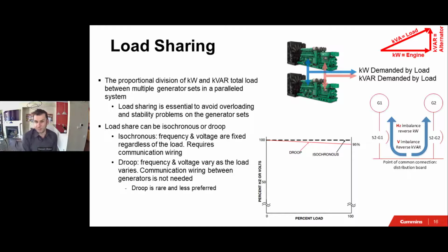Droop, on the other hand, does not require the generator sets to communicate with one another. This is useful, for example, if you have 2 generators from 2 different manufacturers, and some manufacturers have ways to do load sharing between the different generators. If they don't have that mechanism, we have to resort to droop paralleling.